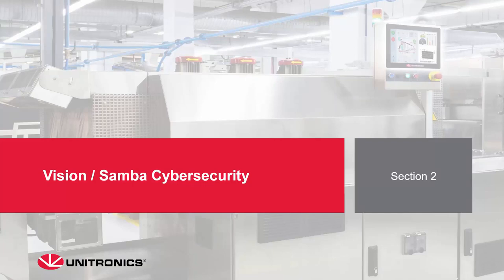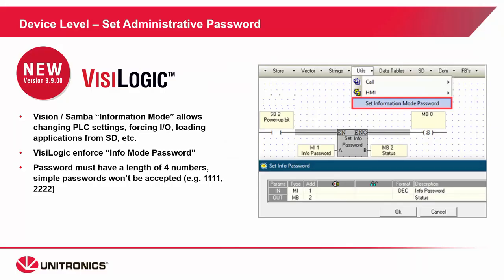Next, we'll talk about Vision and Samba cybersecurity. A lot of these features were added in the new version 9.9.00, available on the website. First, Info Mode access. Info Mode is a backdoor set of screens on any Samba or Vision product. It allows access to things like PLC settings, IP addressing, ports, serial settings. You can force I/O, change tags or operands, load applications from an SD card, and more. In the newest version of VisiLogic, it now enforces an Info Mode password — it's a four-number password, and simple passwords like 1111 will not be accepted.